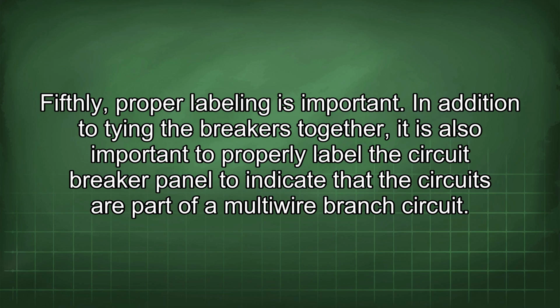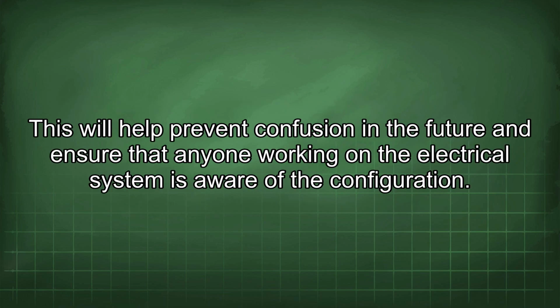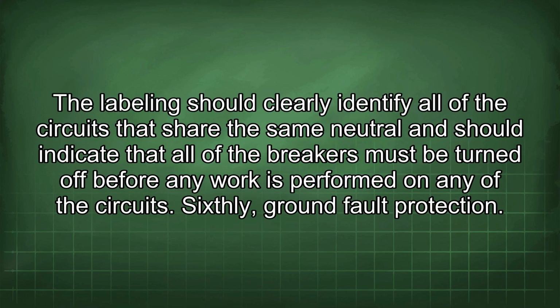In addition to tying the breakers together, it is also important to properly label the circuit breaker panel to indicate that the circuits are part of a multi-wire branch circuit. This will help prevent confusion in the future and ensure that anyone working on the electrical system is aware of the configuration. The labeling should clearly identify all of the circuits that share the same neutral and should indicate that all of the breakers must be turned off before any work is performed on any of the circuits.